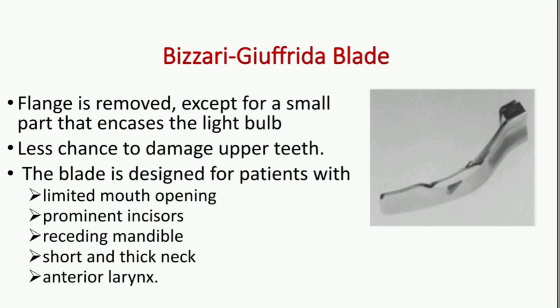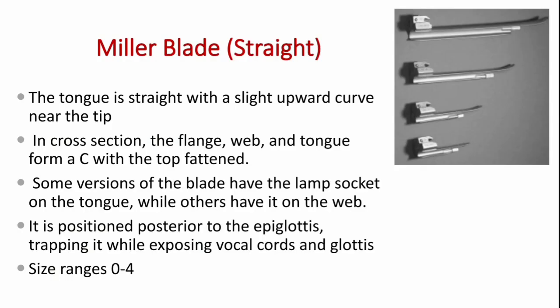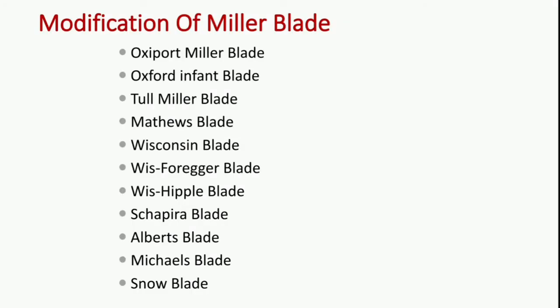The Miller blade is a straight blade commonly used for the pediatric population. The tongue is straight with a slight upward curve near the tip. In cross-section, the flange, the web, and the tongue form a C with the top flattened. Some variations have the lamp socket on the tongue while others have it on the web. It is positioned posterior to the epiglottis, trapping it while exposing the vocal cords and the glottis. The size ranges from 0 to 4. The Miller blade also has its own modifications.